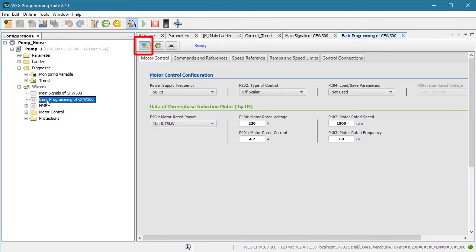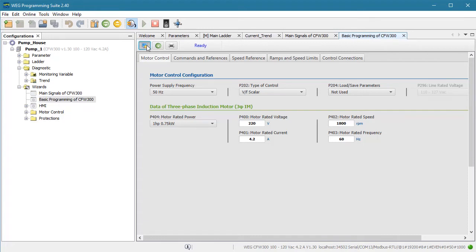Why? Because in monitor mode, WPS is reading the values over and over, right? Well, if a read occurs while you are trying to do a write, the value you are trying to write could get overwritten with the read value and then that read value is what gets written to the drive, which isn't what you wanted. So be sure to exit the monitor mode before trying to write any values.